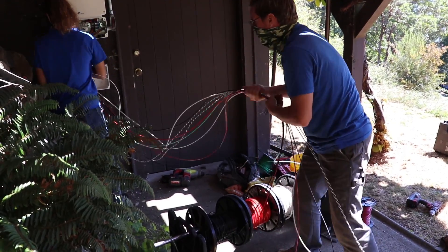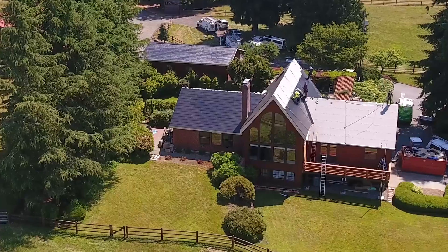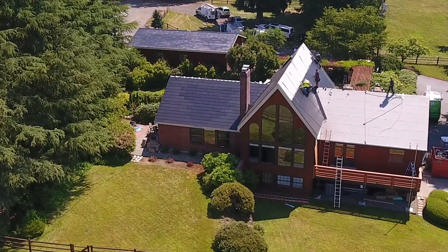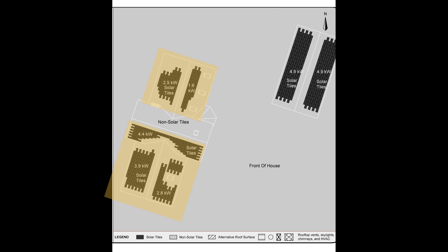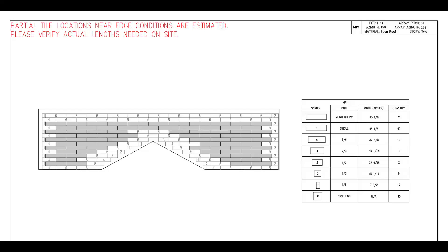The completed roof now produces up to 25 kilowatts of solar power through the PV system, with building-integrated solar tiles on both the main home and detached garage, consisting of 428, 14-cell, 59-watt solar roof tiles, with 47% — around 1,800 square feet — of the roof tiles being photovoltaic. The remaining 53% of the Tesla roof tiles are aesthetically identical to the photovoltaic tiles, but produce no power.